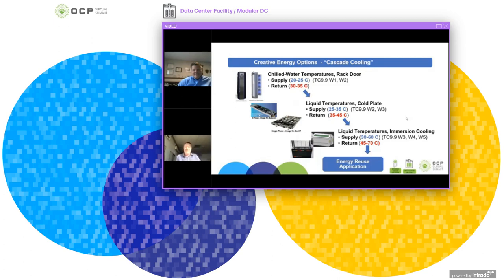What we're showing here is that you could actually run some lower grade heating but cascade it into some of this new technology. So you go back with the view that it allows you to run things like rear door temperatures at lower supply and return. But the important thing is that the return heat can actually become the supply heat for the next thing on the chain.